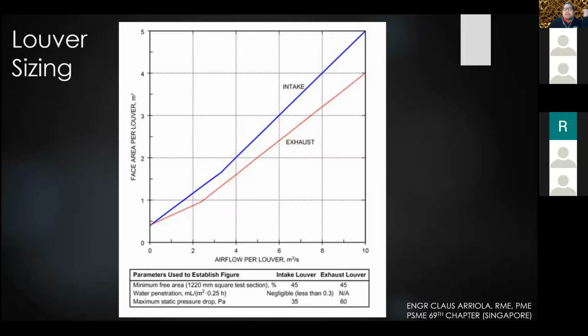Wait, I need to annotate. Then your louver is around 3.3 square meters. But because you have a large volume of air, which can be up to 30 meters cubed per second, you can size it based on Q equals AV. Then take the velocity of this one. So if you want the area, A is equal to Q over V.